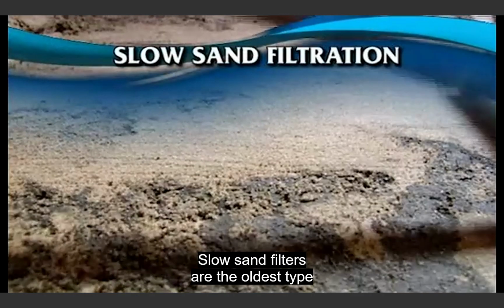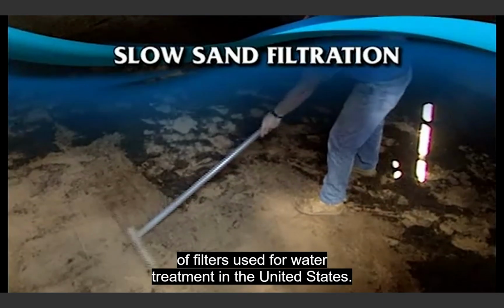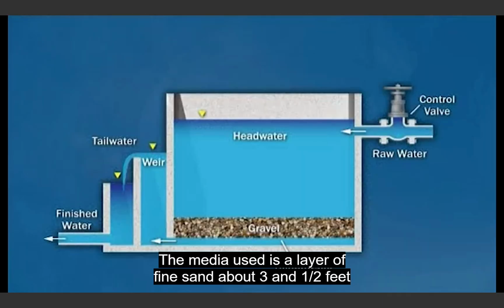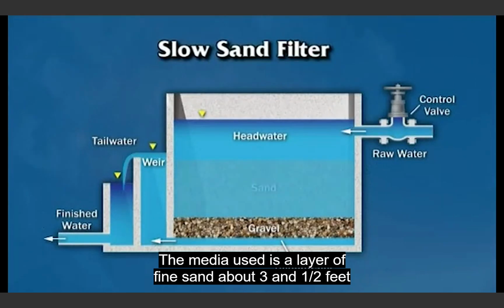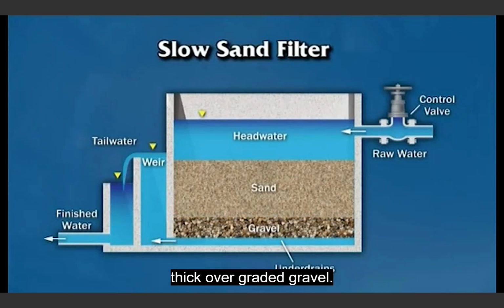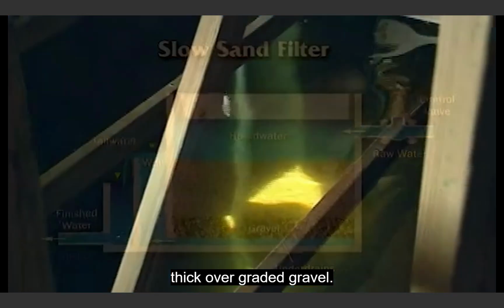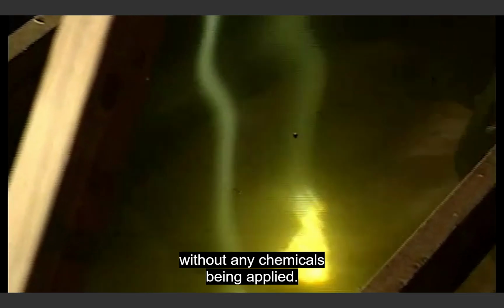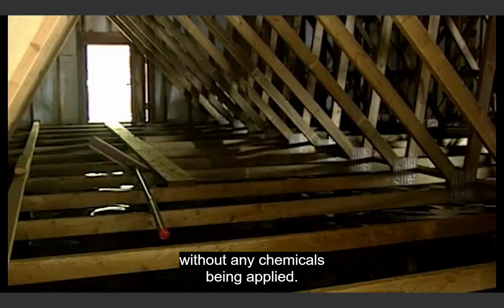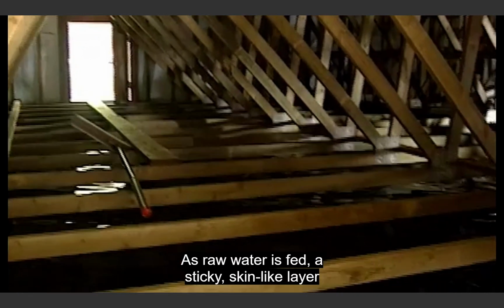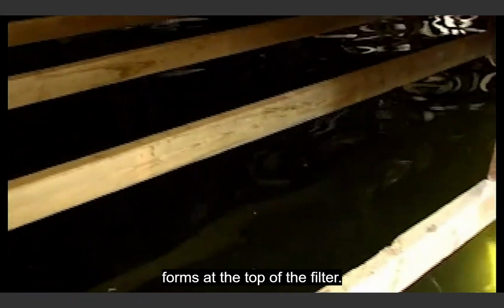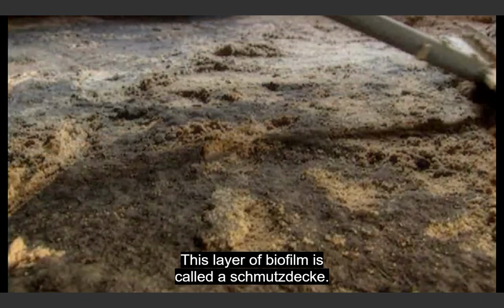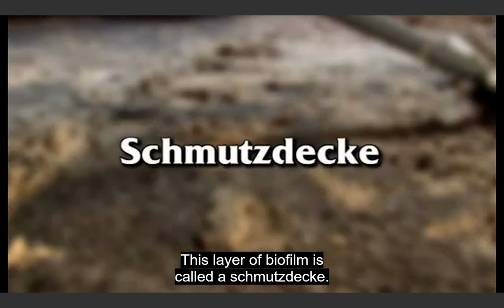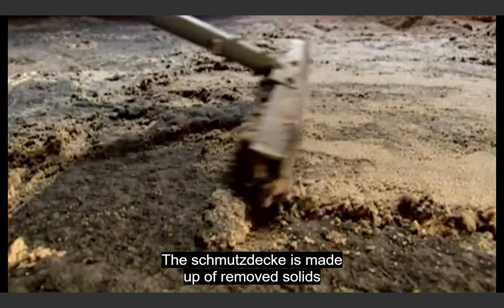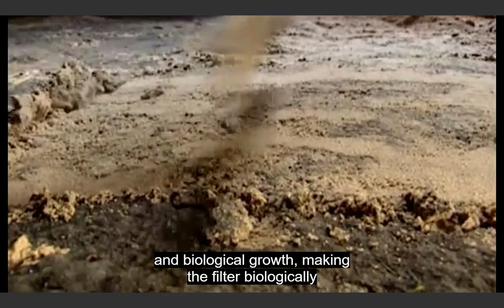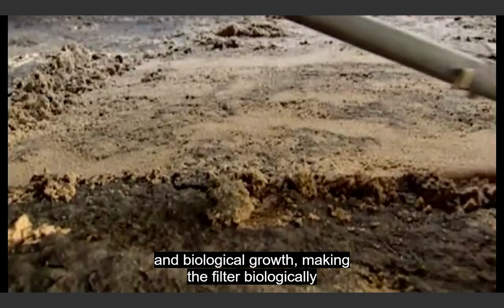Slow sand filters are the oldest type of filters used for water treatment in the United States. The media used is a layer of fine sand about 3.5 feet thick over graded gravel. Water is fed directly to the filter without any chemicals being applied. As raw water is fed, a sticky, skin-like layer forms at the top of the filter. This layer of biofilm is called a Schmutzdecke. The Schmutzdecke is made up of removed solids and biological growth, making the filter biologically active.